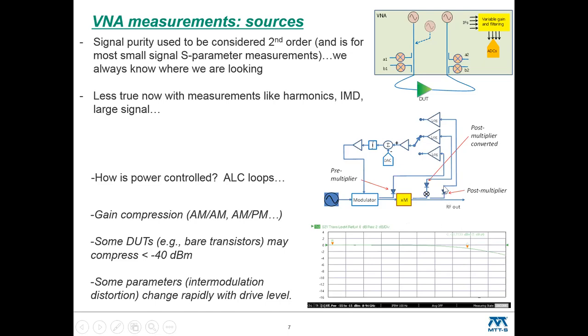The trouble if one tries to do this directly, say in the hundreds of gigahertz, with a single detection scheme like this, is the amount of noise energy you're integrating over that bandwidth can just swamp your available detection range. So that can be a challenge to get good power control, as well as the sensitivity of the detectors over that kind of range, which can be varying and perhaps limited.